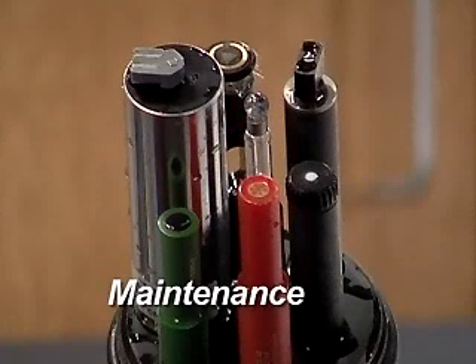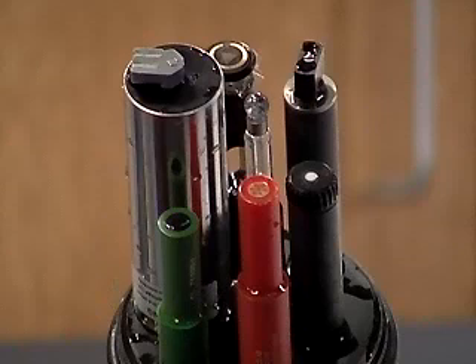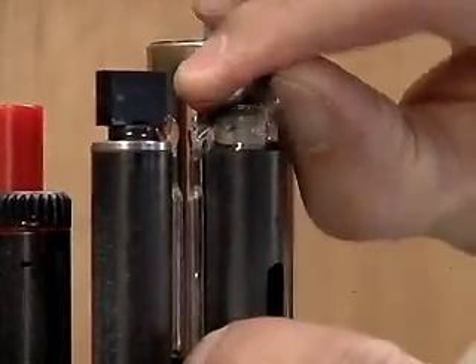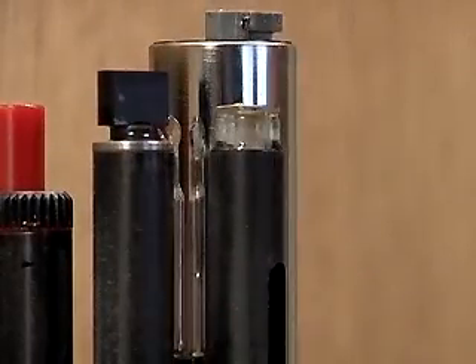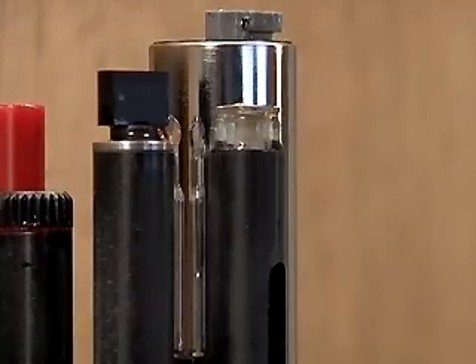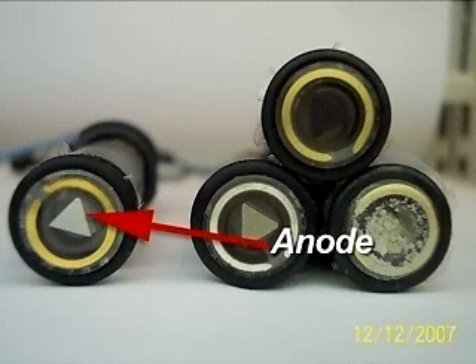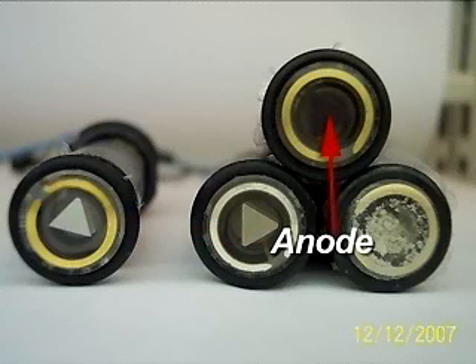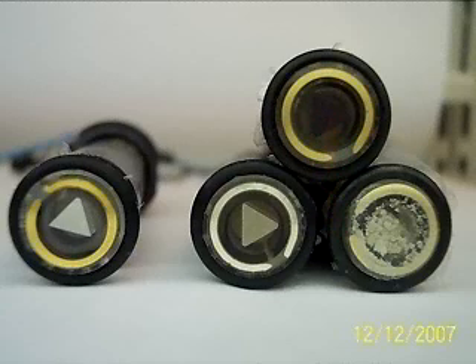Maintenance. The Clark cell membrane and electrolyte must be periodically replaced and the sensor recalibrated to ensure accurate readings. Remove the O-ring at the top of the sensor and discard the old membrane and electrolyte. Check the condition of the electrodes. The anode should be a white or off-white triangle in the center of the sensor. As it ages, it will begin to turn black and may break apart. When it reaches this stage, the sensor must be replaced.